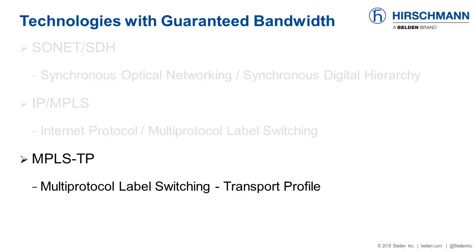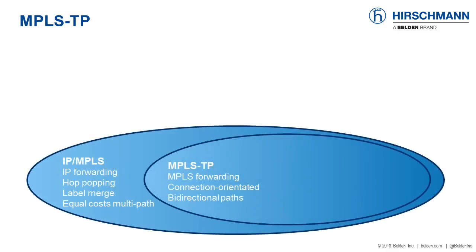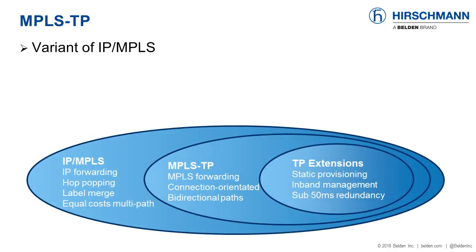There's a third, relatively new option known as Multi-Protocol Label Switching Transport Profile. Here is a high-level overview of MPLS-TP. MPLS-TP is a simplified version of IP MPLS — it uses a subset of the features found in IP MPLS plus some additional features. These include in-band network configuration and management, static network provisioning, and bi-directional communication paths. Basically, these additional features make MPLS-TP an ideal protocol for an industrial network backbone.